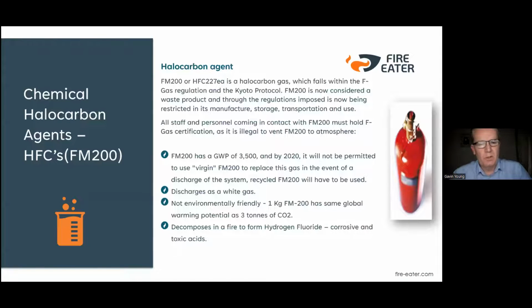So just to talk about chemicals first, FM200 came out of the back of halon. When halon was banned back in 2003, FM200 was the replacement for halon. So it's a halocarbon gas, which falls under the F-gas regulation now under the Kyoto Protocol. It's considered to be a waste product, even though it's still in the marketplace.